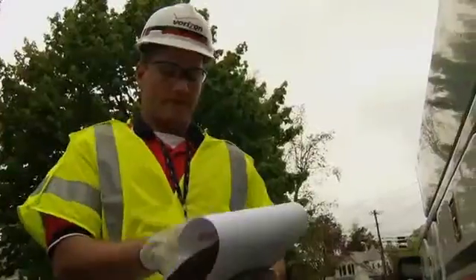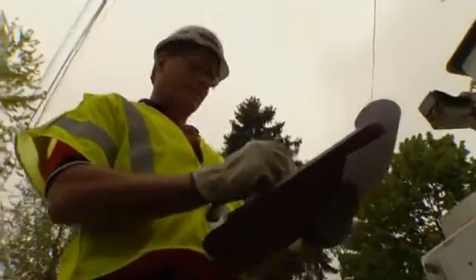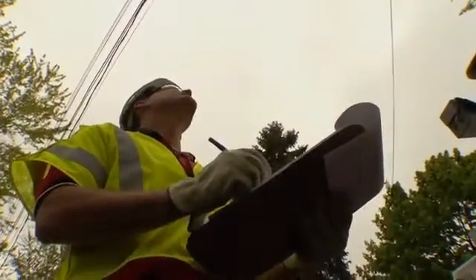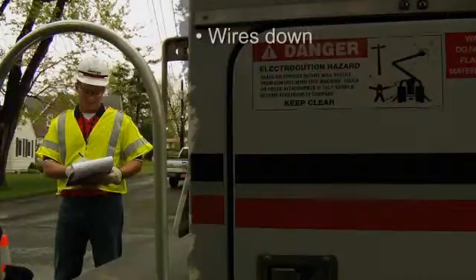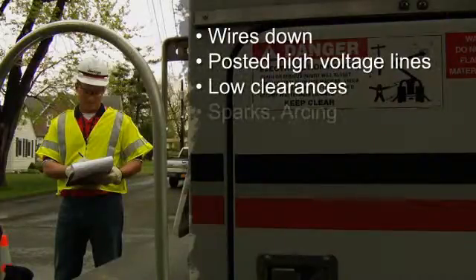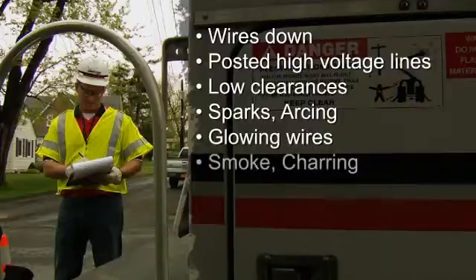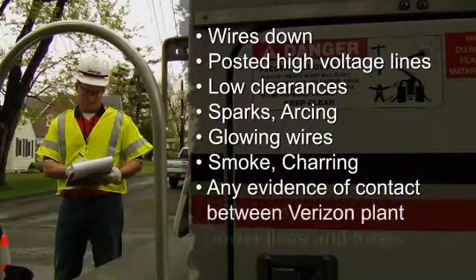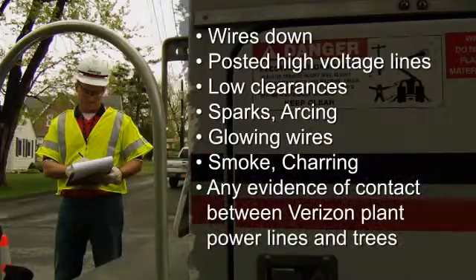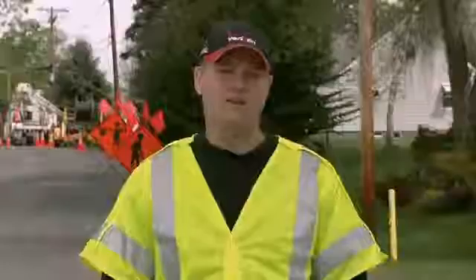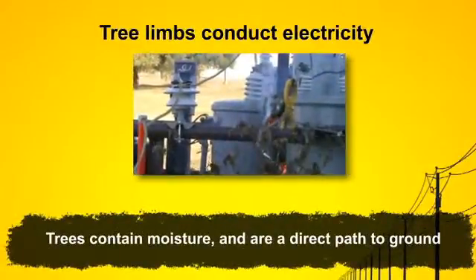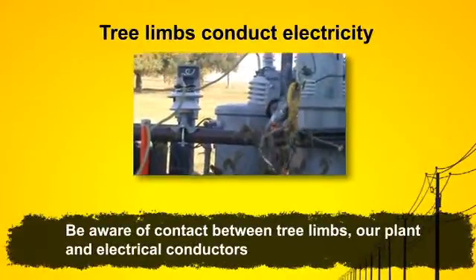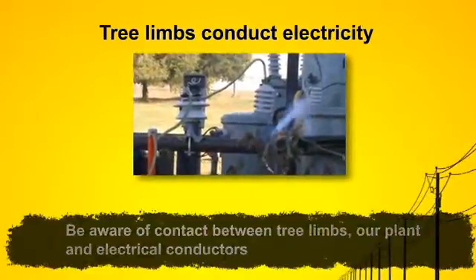As you perform your pre-job survey, there are a number of potential hazards to look out for. Review your work print for any useful information about the power in the area. Look for wires down, posted high voltage lines, low clearances, sparks, arcing, glowing wires, smoke, charring, or any evidence of contact between Verizon plant, power lines, and trees. You might not think that tree limbs are a good conductor of electricity, but make no mistake, they are. They contain moisture and are a direct path to ground. Be aware of contact between tree limbs, our plant, and electrical conductors.